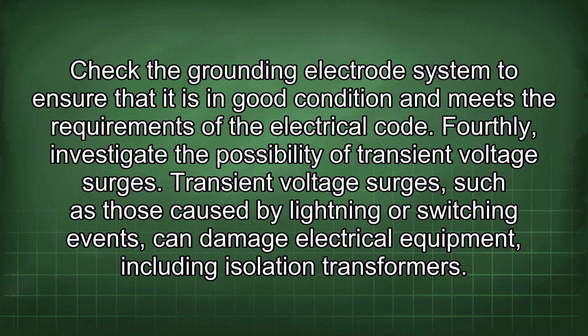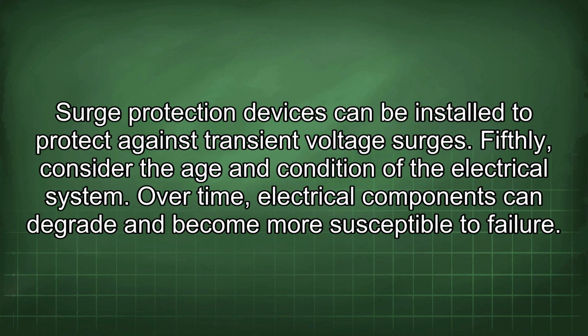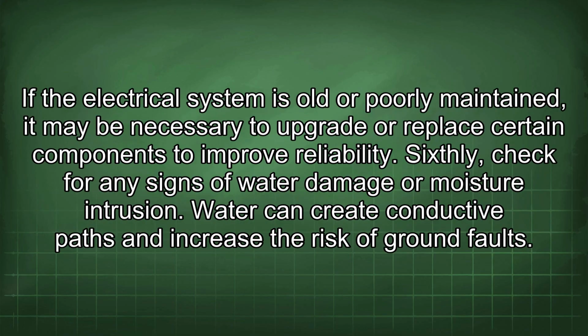Transient voltage surges, such as those caused by lightning or switching events, can damage electrical equipment, including isolation transformers. Surge protection devices can be installed to protect against transient voltage surges. Fifthly, consider the age and condition of the electrical system. Over time, electrical components can degrade and become more susceptible to failure. If the electrical system is old or poorly maintained, it may be necessary to upgrade or replace certain components to improve reliability.